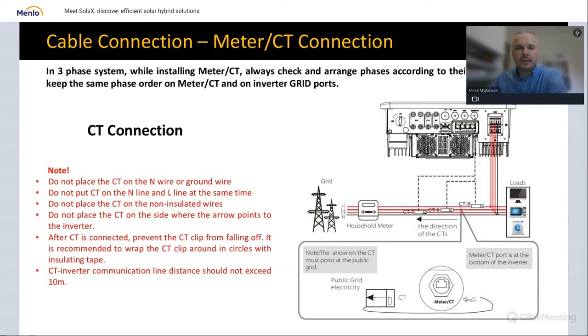And the distance between the CT and the inverter, the communication line distance, after a few years of experience using those CTs, should not be bigger or much bigger than 10 meters. I would say 15 meters is still okay, but 40 or 60 or 100 meters, no, the accuracy really is not good then. So it is always better in those places to use a meter instead of the CT. A meter can go up to 100 meters of communication line, and there will be no problem with sending the communication over that distance.